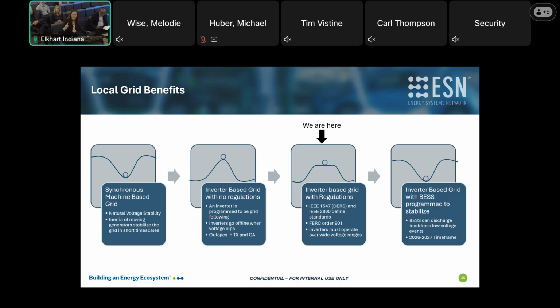That code will never apply to Indiana, because inverters now must be IEEE 1547 compliant if behind the meter, since you're in AEP territory, or IEEE 2800 compliant if in front of the meter. PJM enforces IEEE 2800 starting in 2026, next year, so you're in luck.